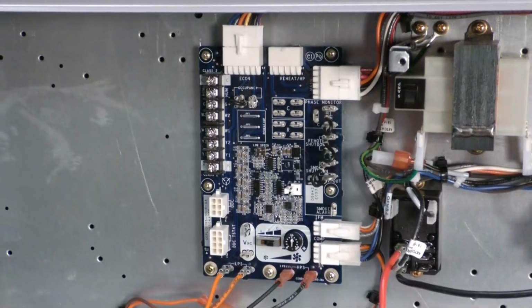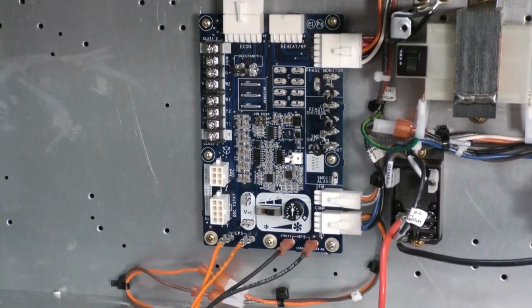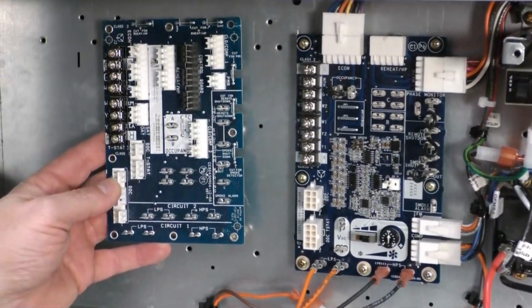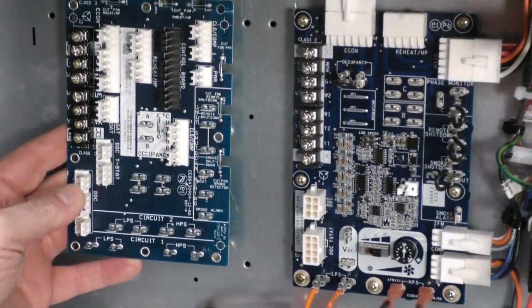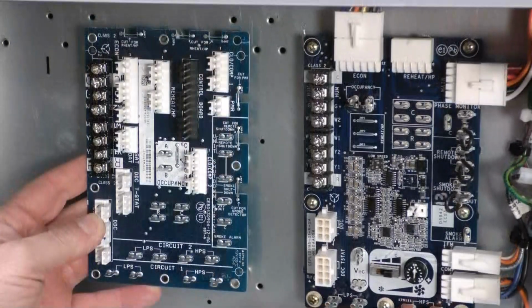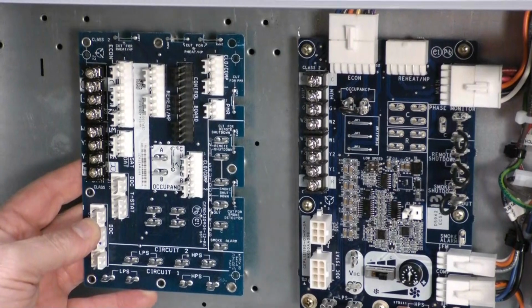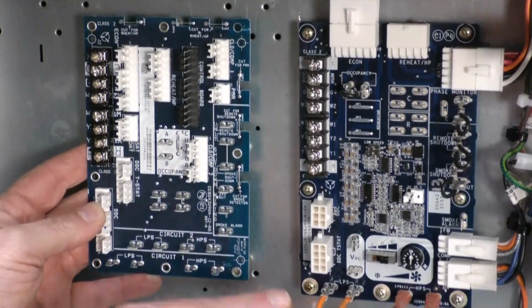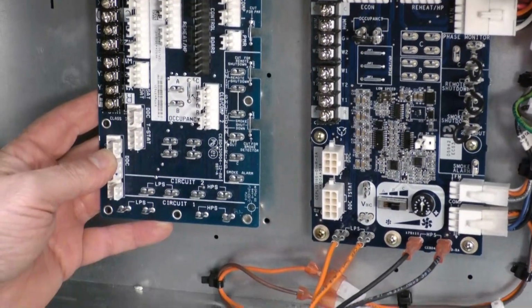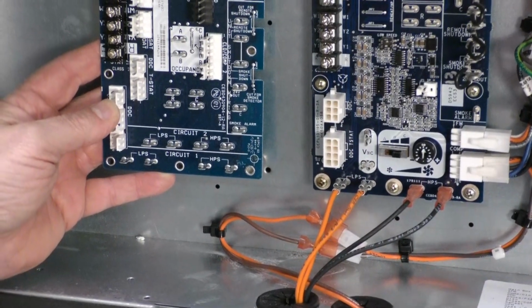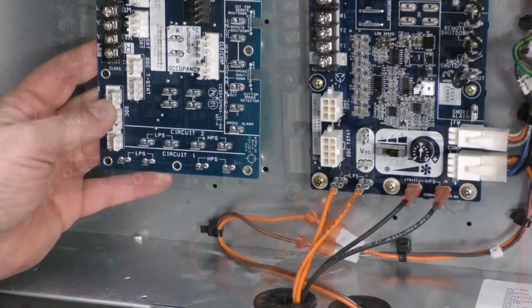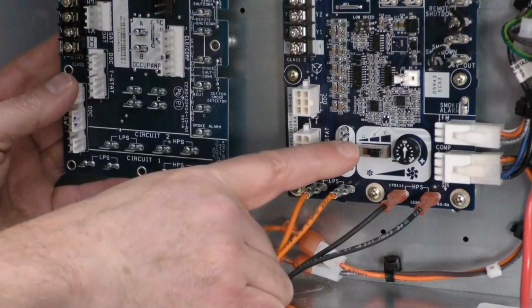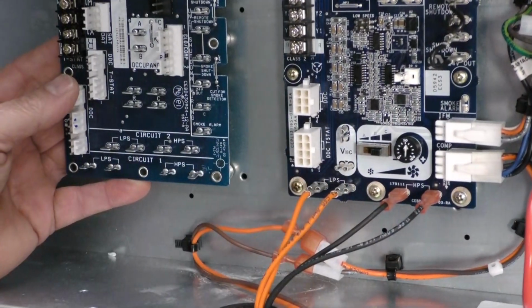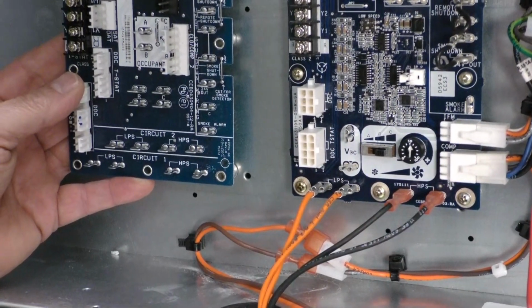For comparison purposes, we're going to show you the current controls terminal board. As you can see, it's about the same size. Our connections are very similar. And just like on the current one here, there are connections for the refrigerant safeties that are out there in the refrigerant circuit. What is different in the new board on the lower portion is the setup for proper indoor fan air delivery.